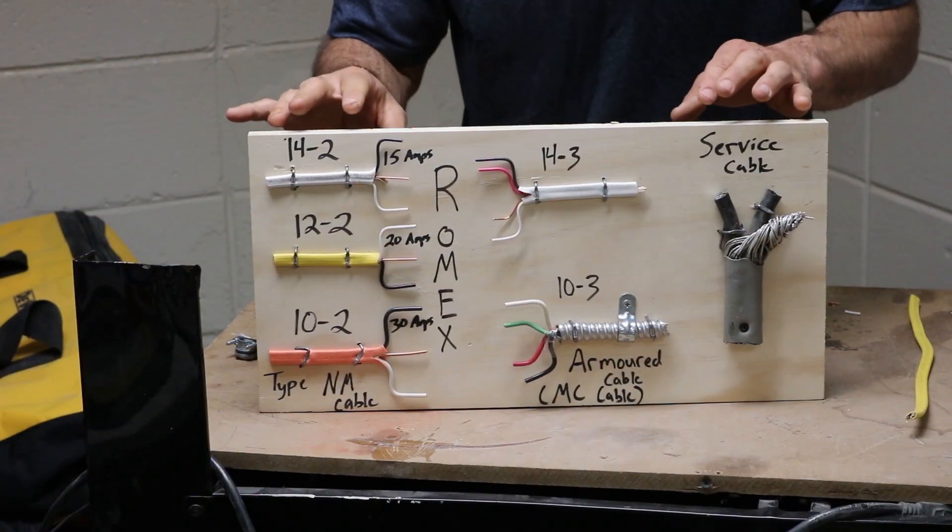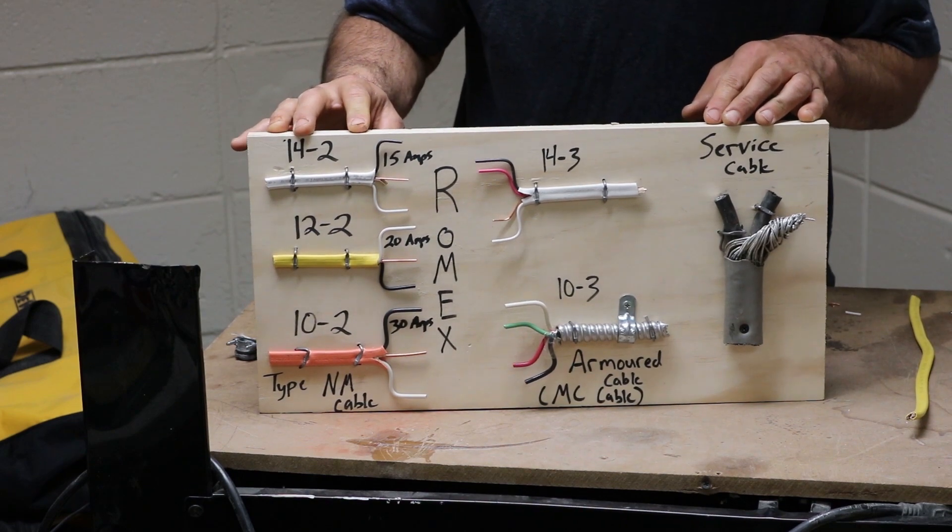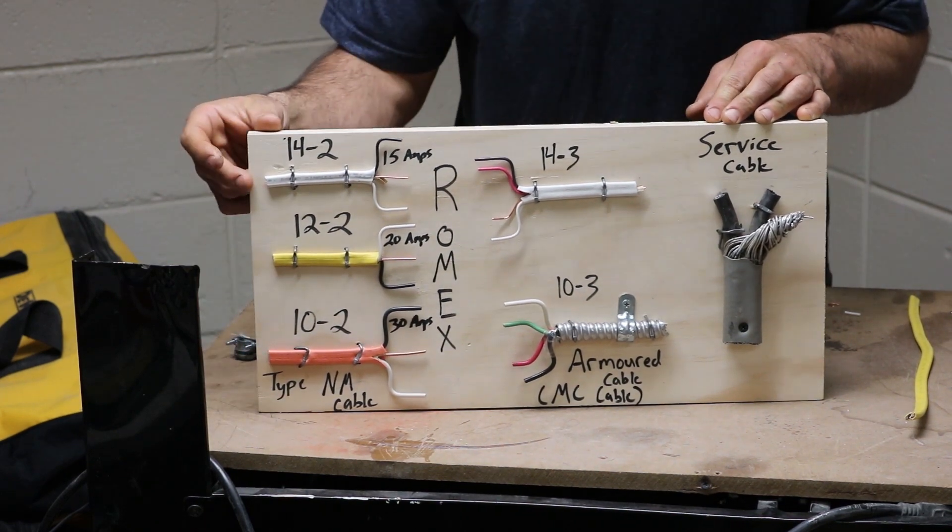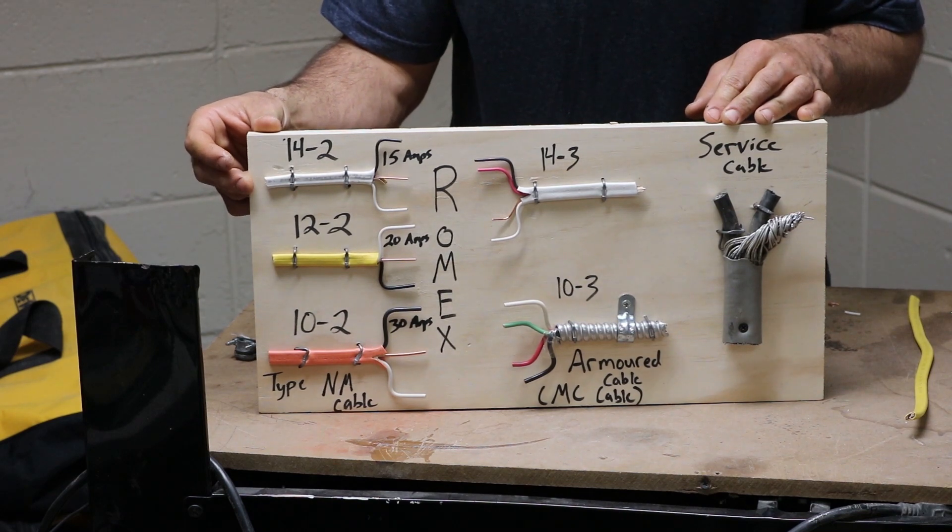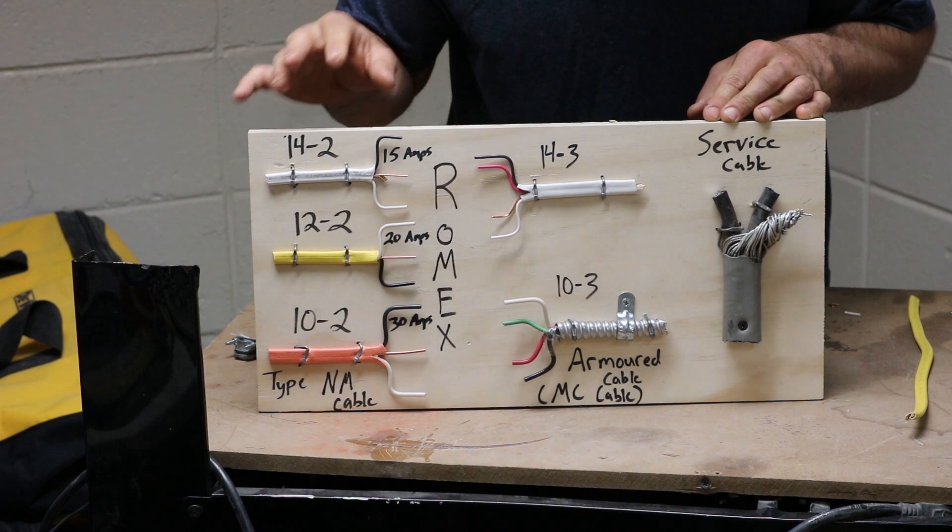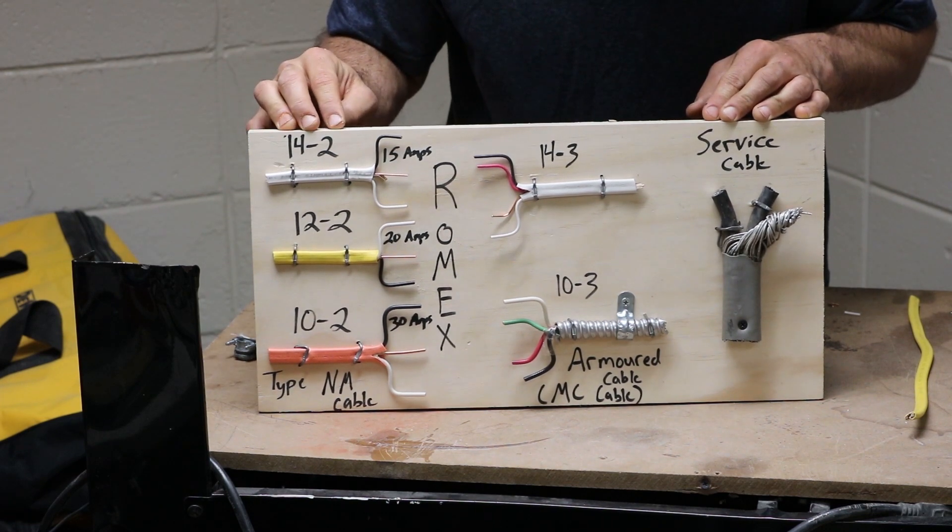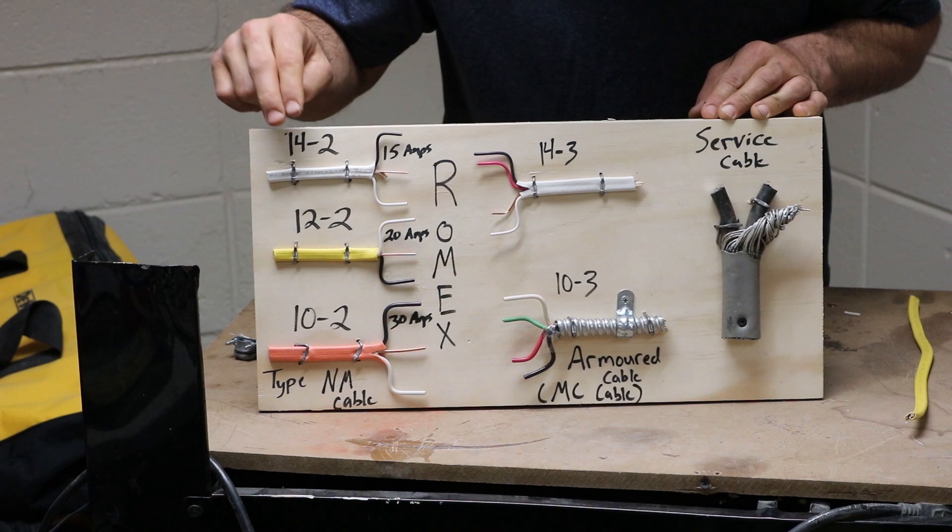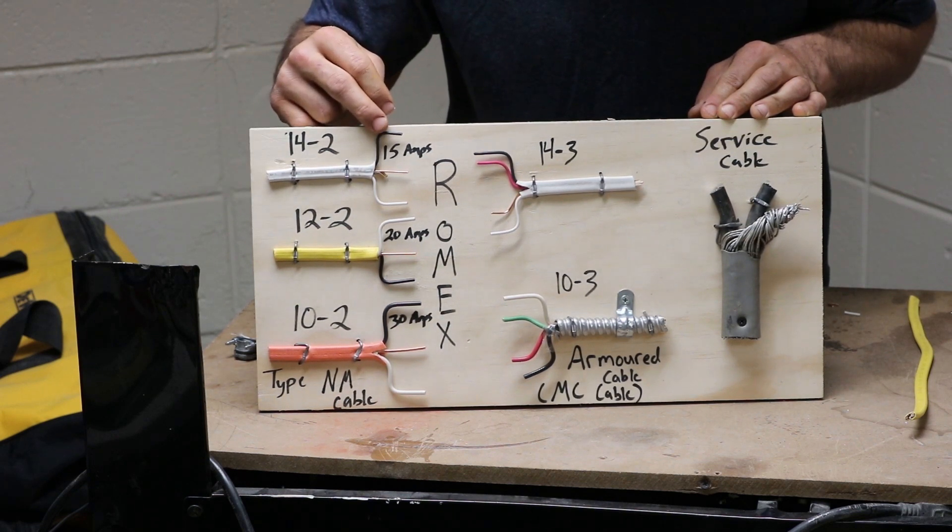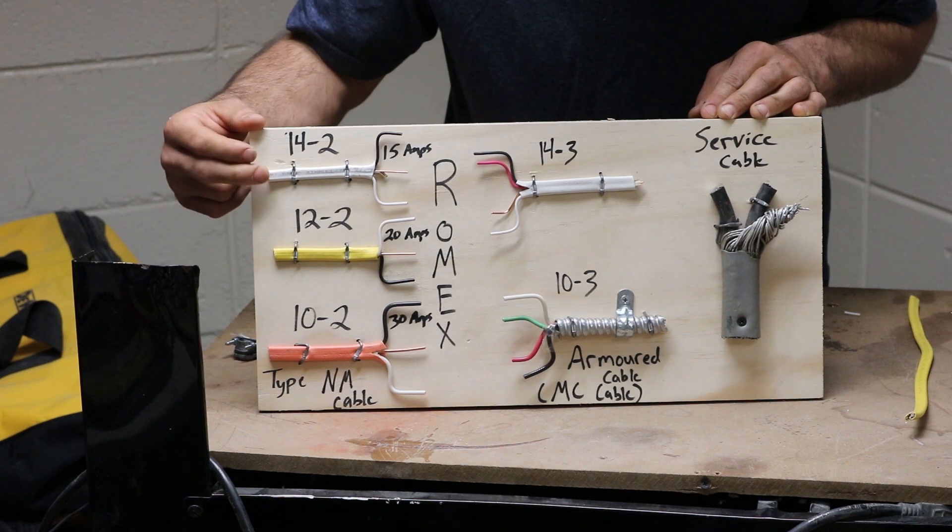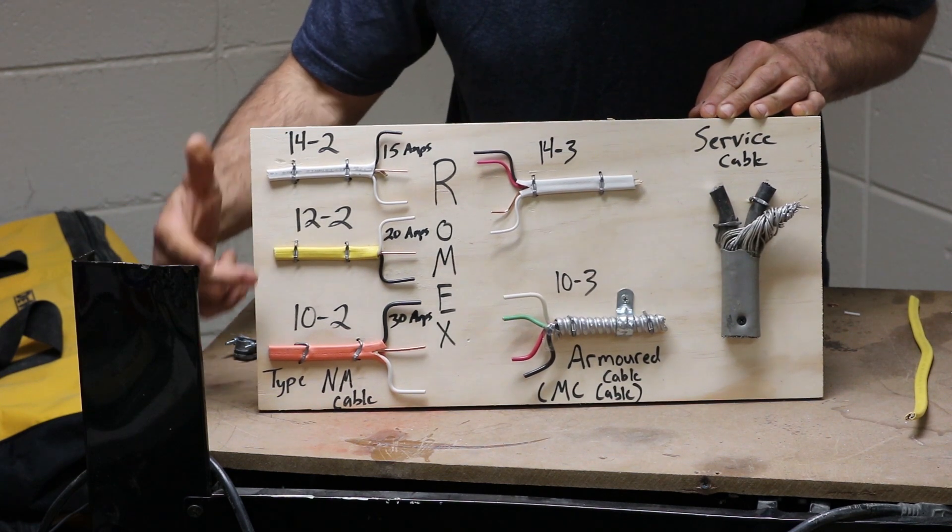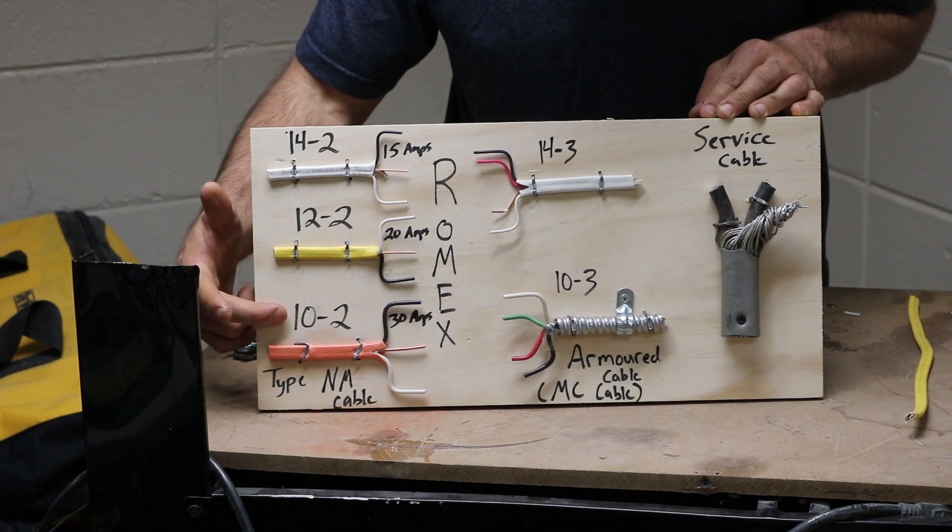Looking at this board, you can see there's a couple of different types of cables on here. On the left hand side, this is all type NM cable or non-metallic, and the trade name is going to be Romex. If you go into Home Depot, say Romex and they'll for sure know what you're talking about. The color of the different Romex denotes what gauge wire it is. White Romex is 14 gauge, yellow Romex is 12 gauge, and orange Romex is 10 gauge.